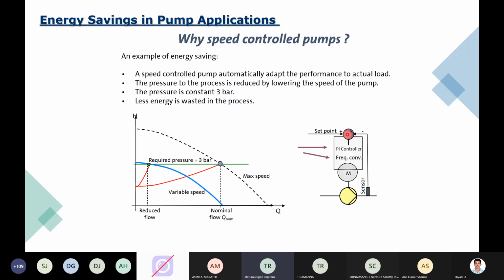Meaning even if your load on a particular day is 10% to 100%, the pump is going to respond to the load situation. At the end of the day, with a fixed speed pump consuming, say, 10 kilowatts and running 12 hours, 10 into 12, 120 kilowatt-hours would be your final power consumption for one day. But with a VFD, obviously there will be an impact. We can say from a minimum of 10% to a maximum of 30% energy saving potential is available here.